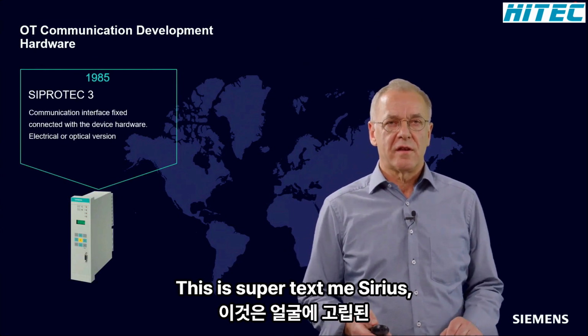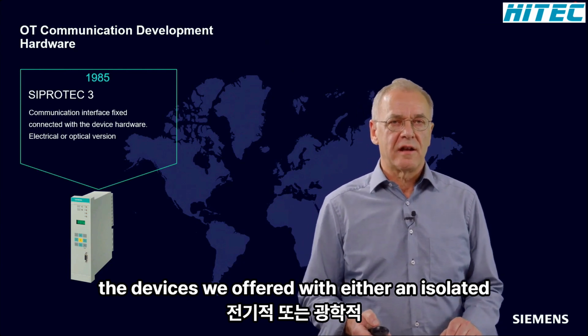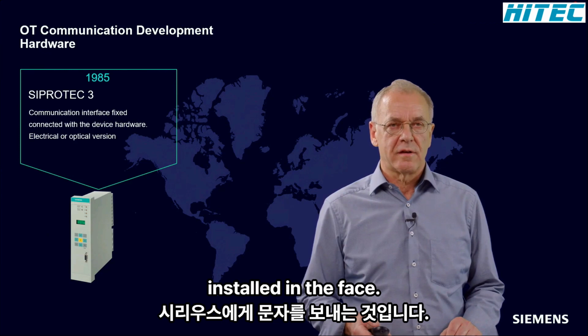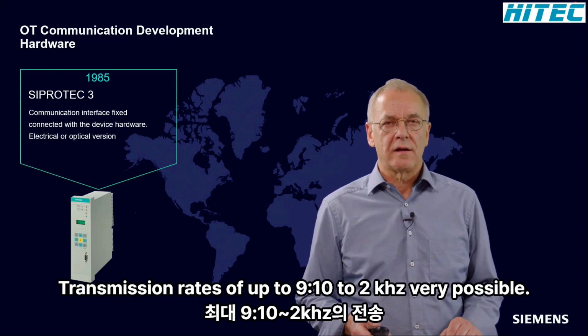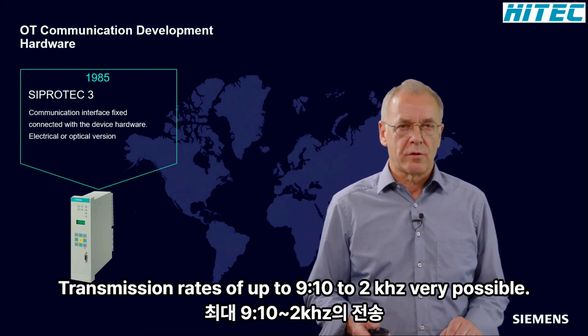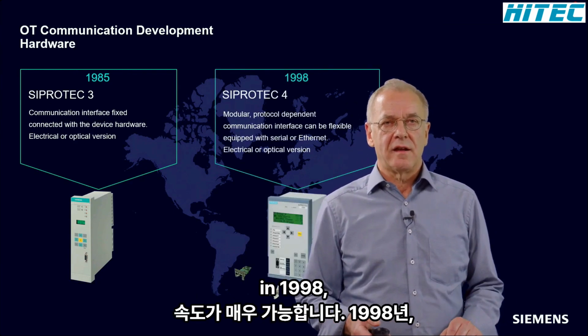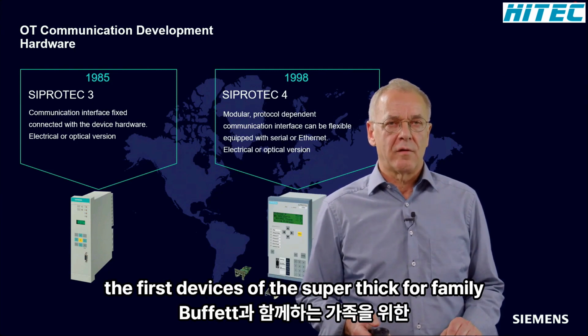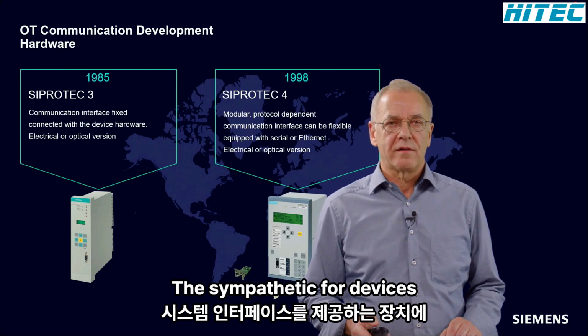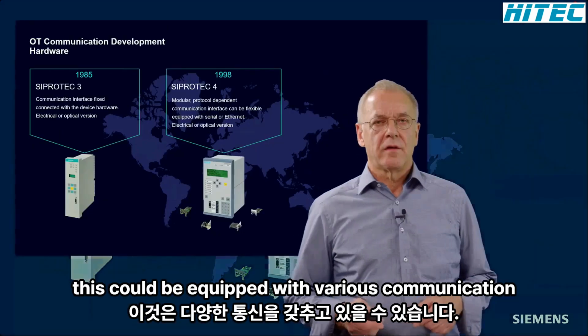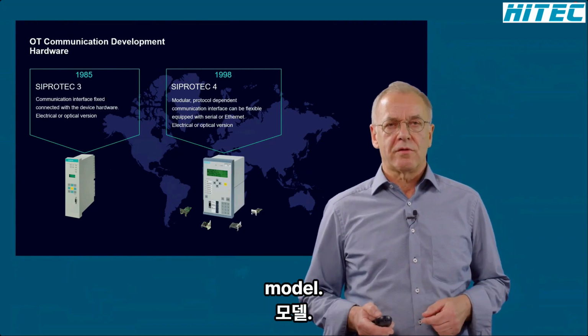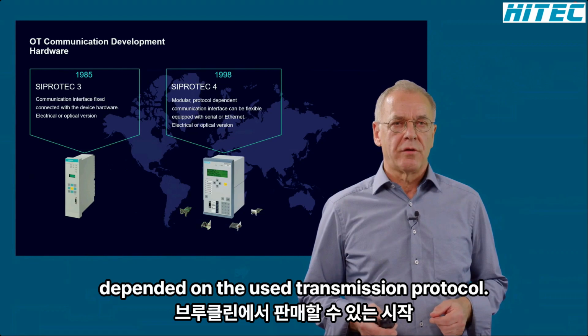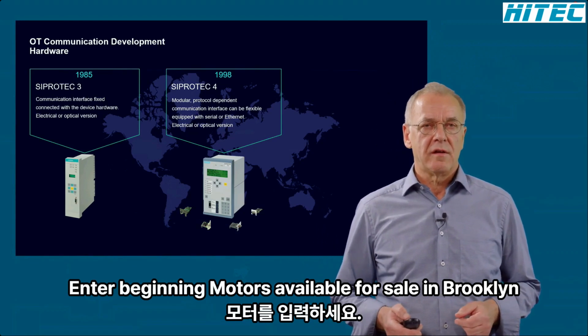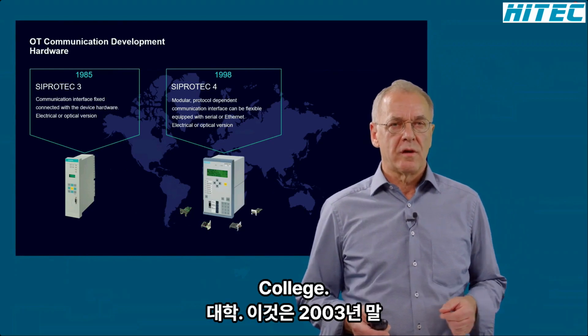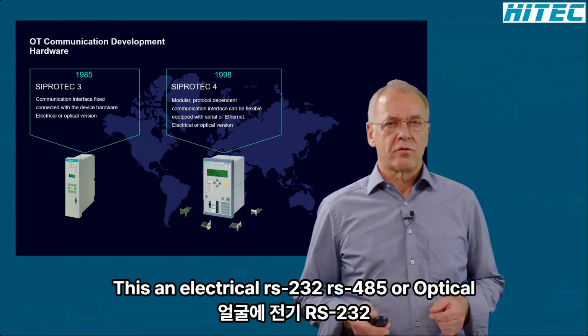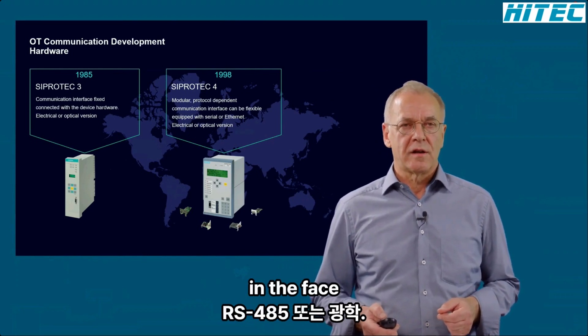With the SIPROTEC 3 series, the devices were offered with either an isolated electrical or optical fixed installed interface. Transmission rates of up to 19.2 kbaud were possible. In 1998, the first devices of the SIPROTEC 4 family were offered. The SIPROTEC 4 devices provided a system interface. This could be equipped with various communication modules. The structure of the modules depended on the used transmission protocol. In the beginning, there were modules available for serial protocols with an electrical RS-232, RS-485, or optical interface.